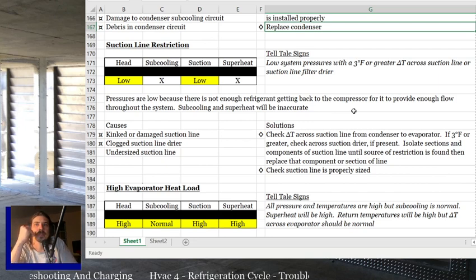But you're going to have low head pressure and low suction pressure. You're probably going to have low subcooling, and you're probably going to have high superheat, but depending on where you measure it, it could look like really low superheat. The problem is the suction line is colder than the indoor temperature, so you can't say, oh, it's below ambient, so I've got a restriction. It doesn't really work like that, so it can be a toughy to find sometimes. Basically, your subcooling and superheat are irrelevant because you're not going to know what they should be, especially the superheat, because there's a restriction in the line.